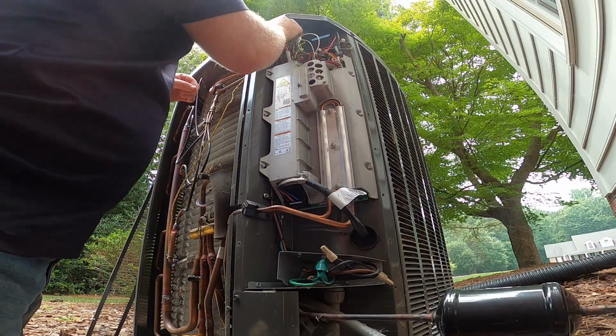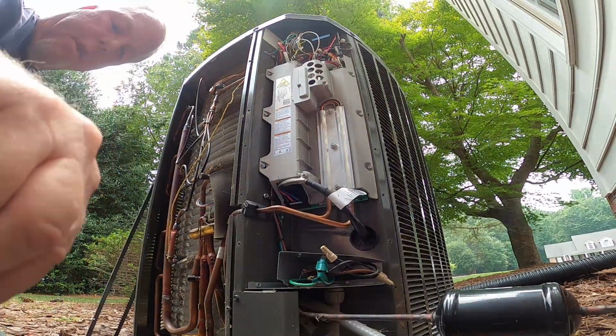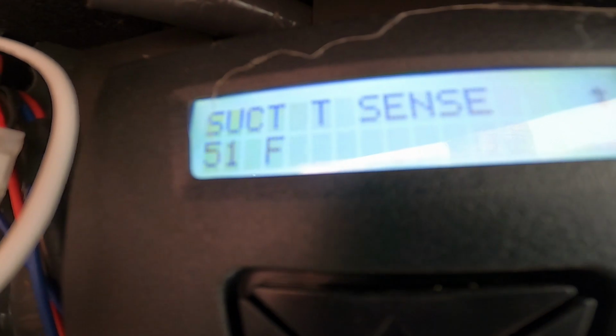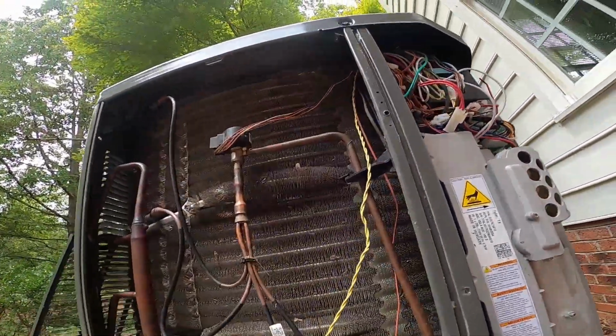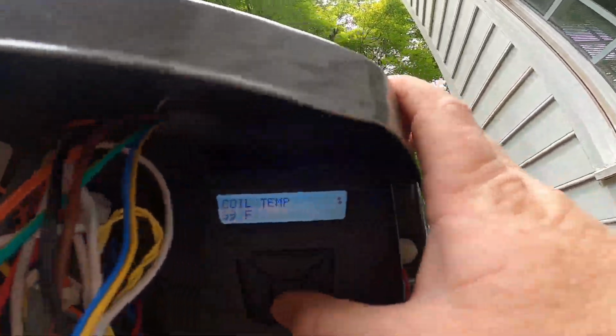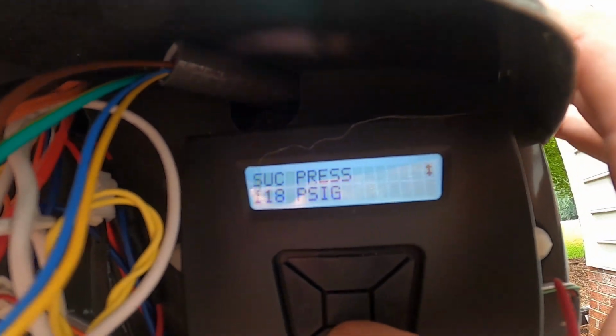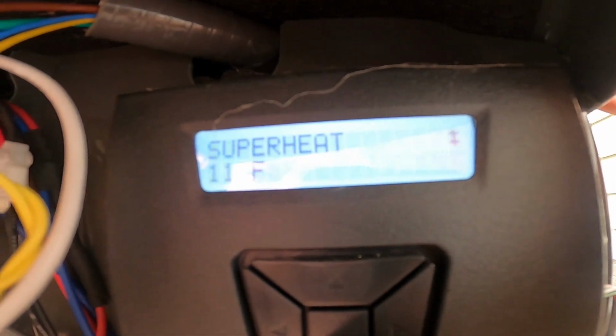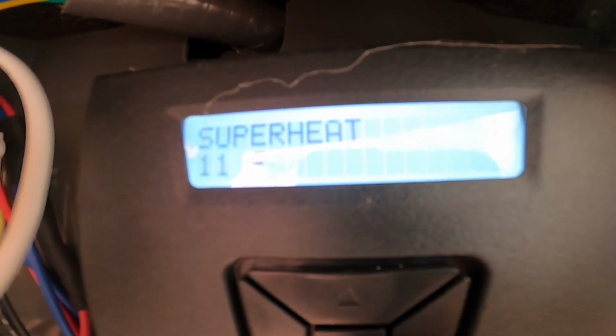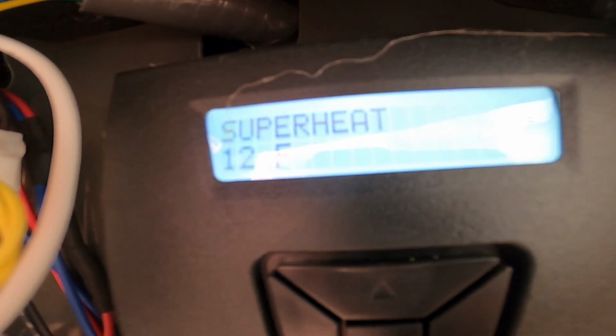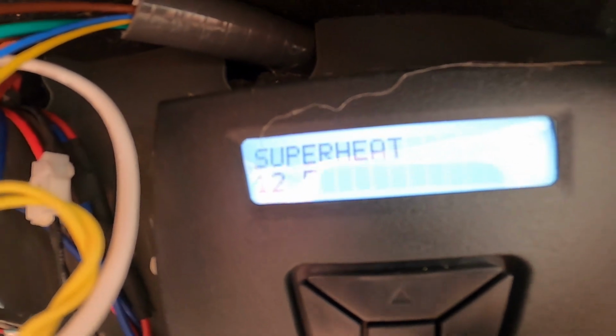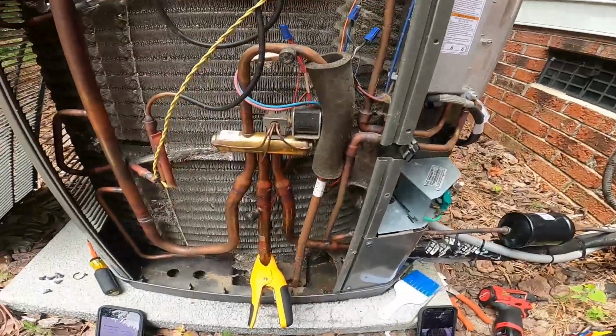Because I'd hate for it to be a drive issue. And it usually isn't. It's usually a sensor. So now, voila, new sensor. We are reading 51 degrees. We'll scroll back up real quick. We got a suction pressure of 118, and it's giving us an 11 degrees superheat right now on this system. He's got it set at 12 degrees superheat. It's set at 70 degrees in the house, and it's maintaining temperature. It was running, it was cooling, it was just showing that fault.